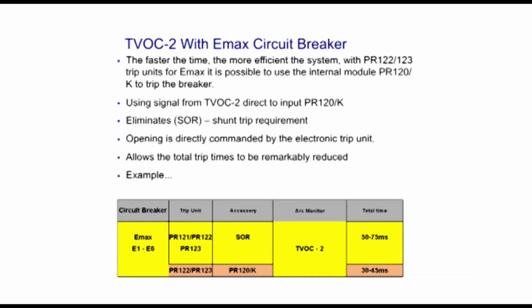If you pay attention to the table below, we've got two sets of tripping options. One is with the shunt trip release, which gives you a tripping time of 50 to 75 milliseconds before the breaker trips. The other is with our PR120K, which is a signaling module integrated into the breaker. So you get a much shorter tripping time, 30 to 45 milliseconds. Because it is integrated with the breaker, the protection relay controls the tripping of the breaker directly. Hence, you're able to achieve 30 to 45 milliseconds.